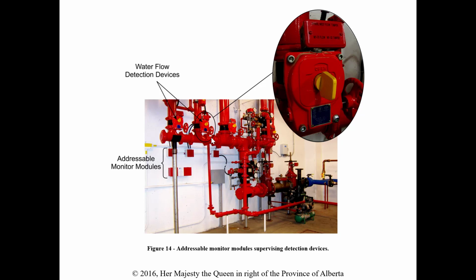So the monitor module is one where we basically have an interface now between the CPU and the fire alarm system using these addressable systems, but with a non-addressable piece of equipment. So this is basically just going to give it an address so that we know if something's happened. And we have these in our lab too, so we're going to see examples of these. Basically it's just monitoring like a supervisory scenario in your system.